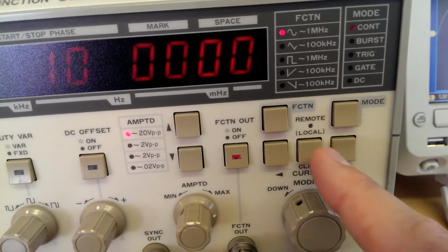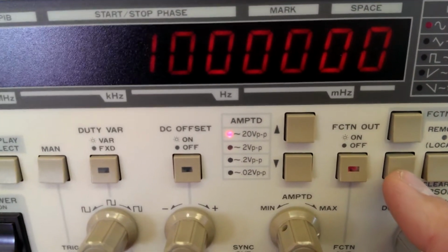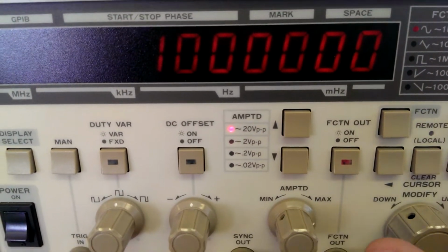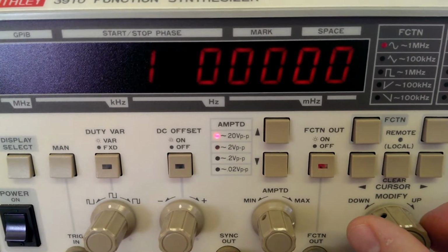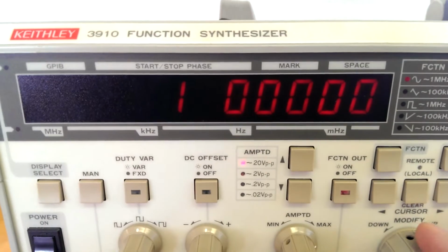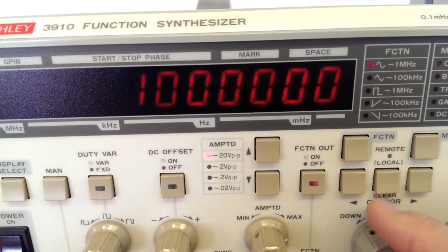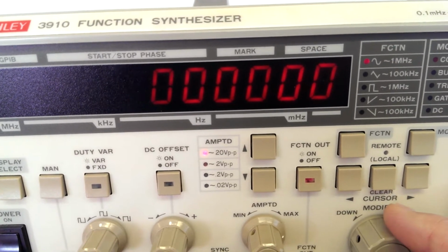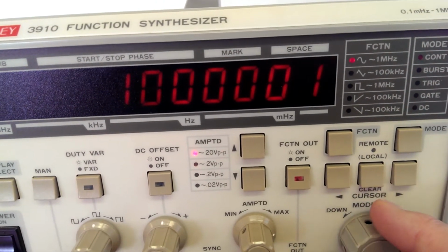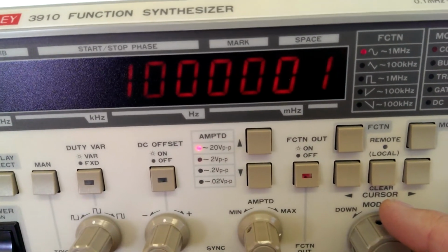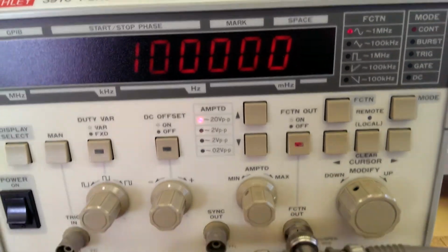The way to change that is, if you look here, there's a knob, and above the knob there is a left and right cursor. As you can tell, as I push the left cursor, I move to the left, and if I adjust the knob, you can see that the voltage changes, or not, I'm sorry, the frequency changes. Since I want it set to 100 hertz, I'll leave it at 100 hertz. Again, that's 200, 300, 400. And you can move the cursor to any point. If you want to set it to 100.0001 hertz, I just did. So we're going to leave it at 100 hertz.